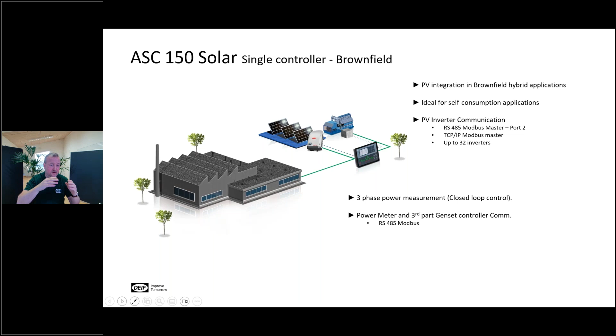It's the same topics and wording here. The only difference is that we allow up to 32 inverters on the same controller. And again, of course, we have the three-phase measurements, so we are also able to do a kind of closed loop control. So if one of the inverters is not performing as expected, by broadcasting the power set points and so on, we can increase that so the others will cover what the one or two inverters are not performing.